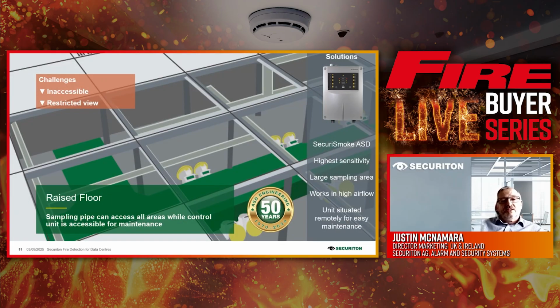Equally, the reverse applies in the raised floor, again potentially with lots of cabling, equipment, and fire risk. It's very important to have high sensitivity, early warning smoke detection using ASD, but also, again, there's maintenance value here. Access can typically be done just from the aspirating smoke detector box, without disruption to a raised floor that's likely very congested with cabling and sensitive equipment. Maintenance can be done safely outside the raised floor, and dare I say, it might also be a little bit cheaper.